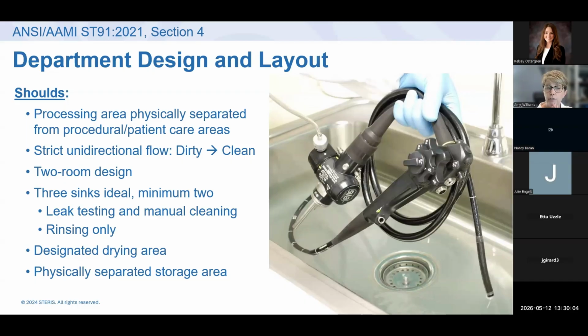Ideally, in your departmental design, again, ideal is 3 sinks: 1 for leak testing, 1 for manual cleaning, and a 3rd for nothing but rinsing, just dedicated for rinsing. Again, older places don't always have 3 sinks, some people don't even have 2 sinks. In that case, the guideline says a minimum of 2. So you can do leak testing and manual cleaning in one, and have a dedicated sink for rinsing only. If you only have one sink in the department, you can use that sink with a basin, or that sink with 2 basins.